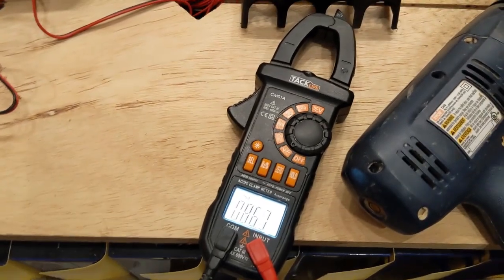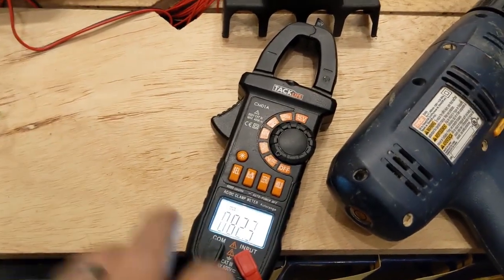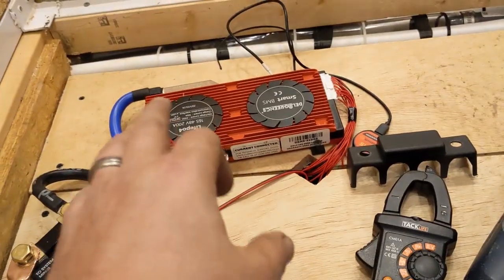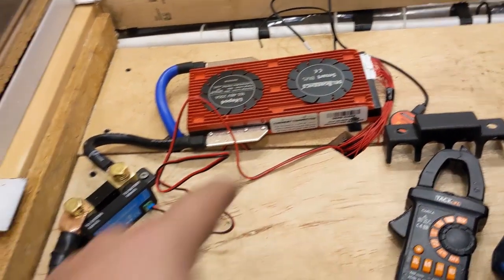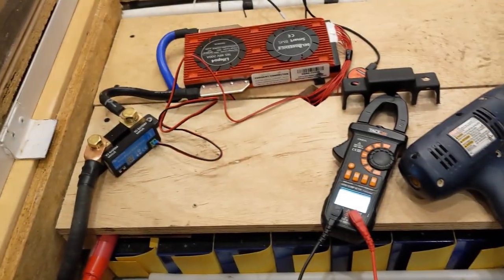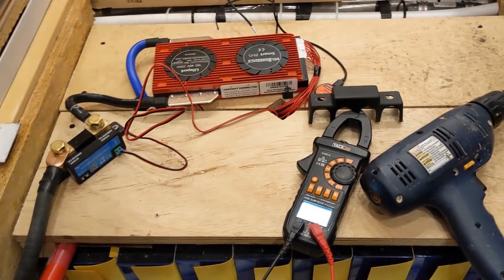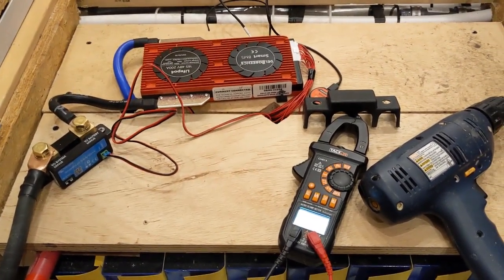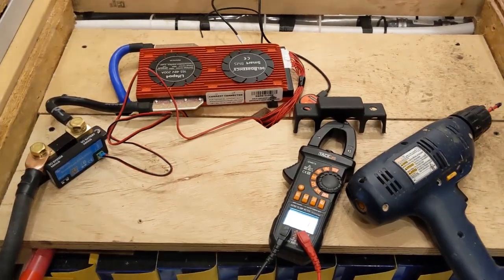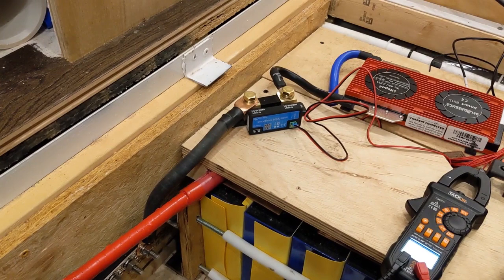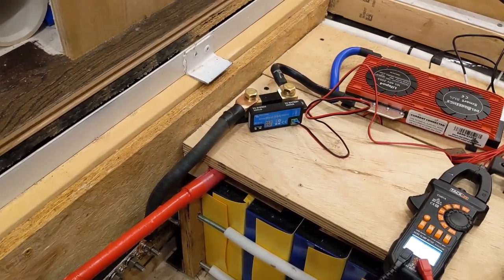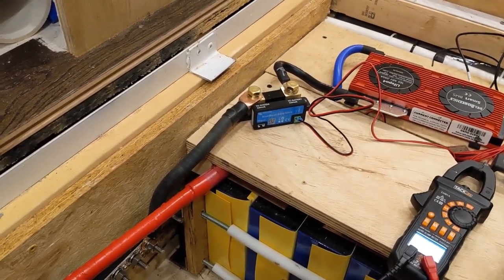Okay, so I'm running some multimeter tests. We're going to start from the battery side, the blue cable there. I'm going to touch the metal there to right here before the switch, see what our voltage is. Alright, so that reading was 54.1. I'll have to do the math and see what the average cell voltage is, divided by 16. Okay, so that 54.1 is an average of 3.38 per cell, which is still a good mid-level charge on the cells.